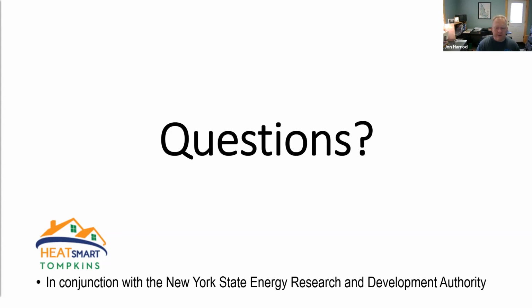I'll provide a link in the notes, but they have an excellent study on cold climate performance of heat pumps. They found dramatic differences in efficiency from one install to another, and a lot of this had to do with proper sizing of the system and proper occupant education. The best systems were hitting a COP of 2.9 and up, but some systems that were oversized or poorly controlled had COPs down in the 1 to 2 range for the whole season, which is kind of miserable. A lot of our learnings are focused on how we can avoid that outcome and help them achieve their rated efficiency.